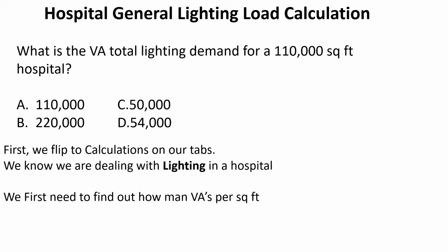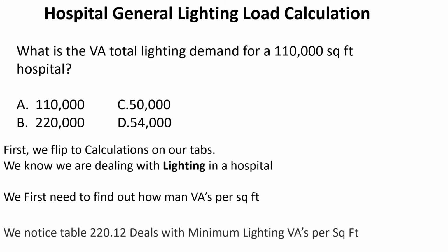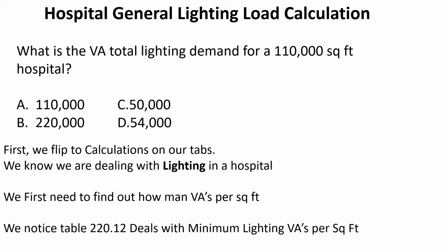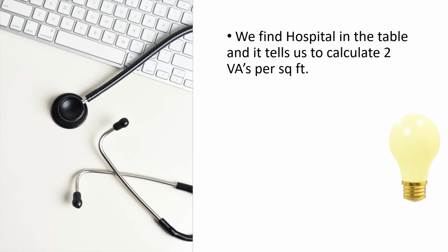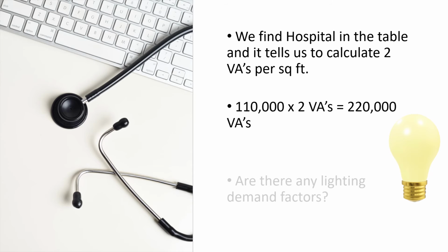We know that we're dealing with lighting in a hospital. First, we need to find out how many VAs per square foot it is. We notice that table 220.12 deals with minimum lighting VAs per square foot. We find hospitals in the table, and it tells us to calculate 2 VAs per square foot. We take 110,000, multiply it by 2 VAs per square foot. That is going to give us 220,000 VAs.